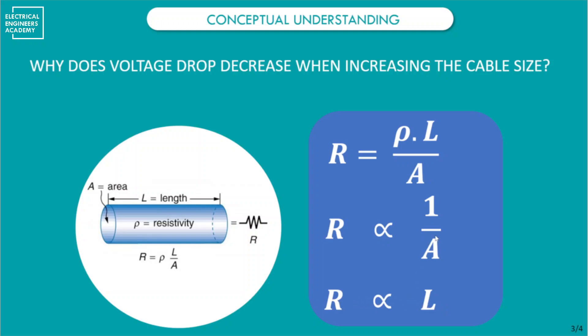The bigger the cross-section of the cable, the less resistance. So in order to overcome the voltage drop occurring in a cable of a certain size, we have to increase its cross-sectional area, which will ultimately reduce its resistance and the corresponding voltage drop. Similarly, the longer the cable, the more the resistance and the more the voltage drop.